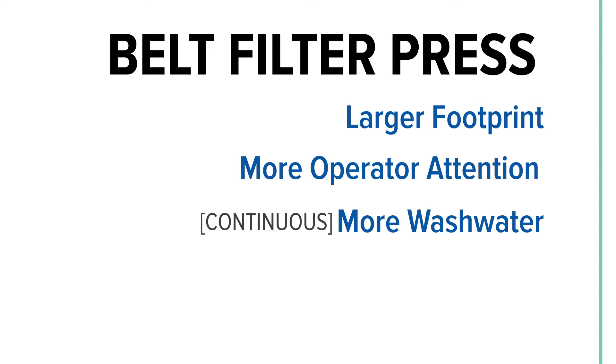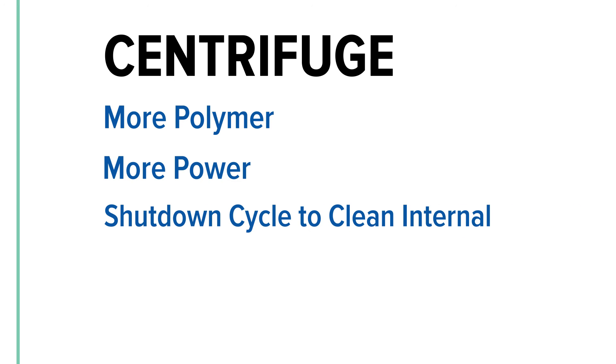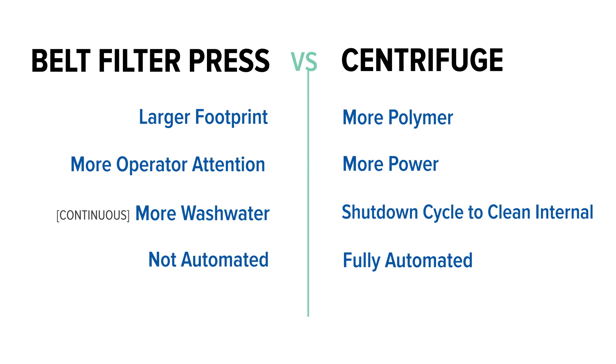The belt press uses a lot of wash water, and the wash water needs to be continuous. For the centrifuge, wash water is only required during the shutdown cycle to clean the internal components. The centrifuge is fully automated, whereas the belt press is not.